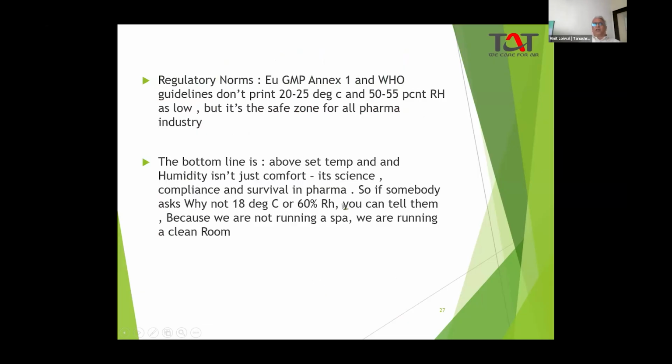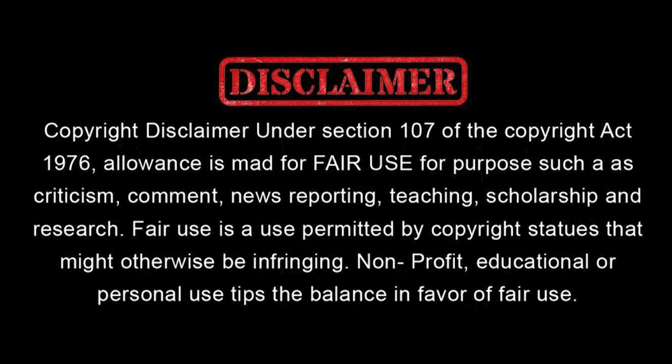As per regulatory norms, EU GMP Annex 1 and WHO guidelines don't mandate 20 to 25 degrees and 50 to 55 RH as limits, but it's the safe zone for the entire pharma industry. The bottom line is that set temperature and humidity isn't just comfort, it's science, compliance, and survival in pharma. So if somebody asks why not 18 degrees centigrade or 60% RH, you can tell them we are not running a spa, we are running a clean room. These are the strict norms to be followed while designing a clean room. Thank you.